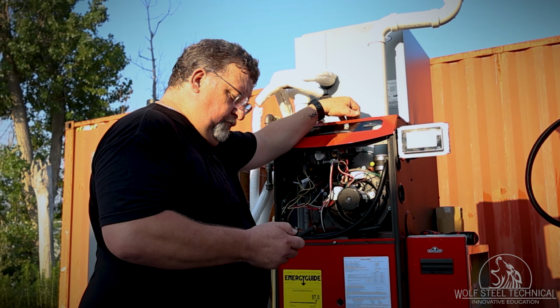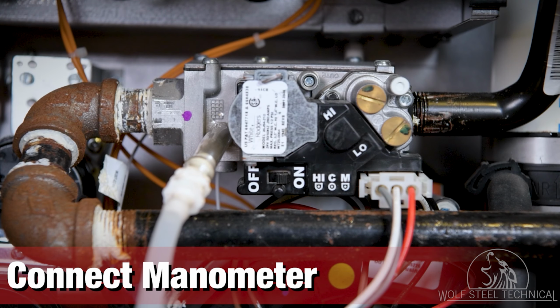If the temperature is within operating temps and the switch has tripped, then the switch will need to be replaced. In addition to this, check the inlet and outlet pressures going to the furnace to ensure they are within the acceptable parameters. A video is linked in the description outlining how to perform this check.